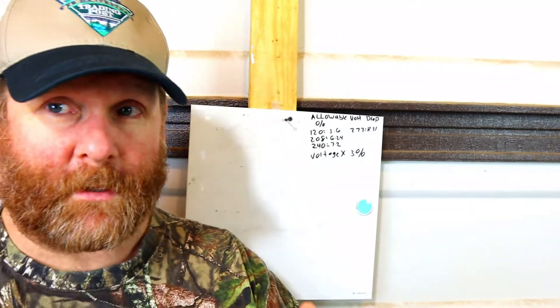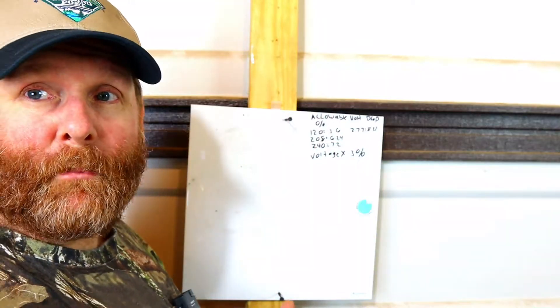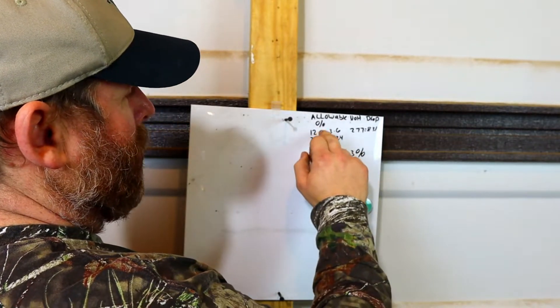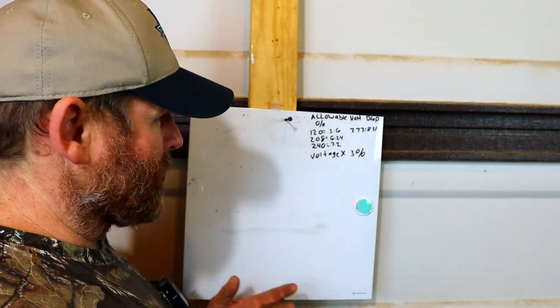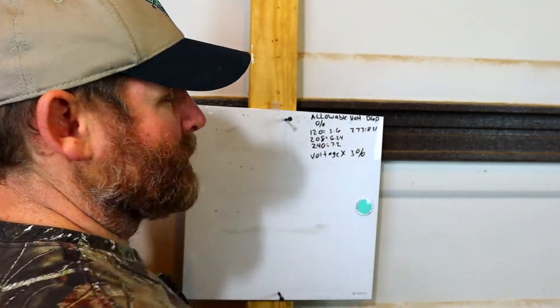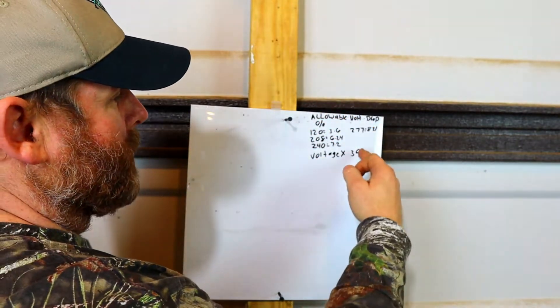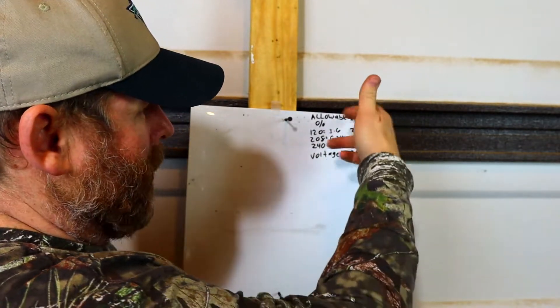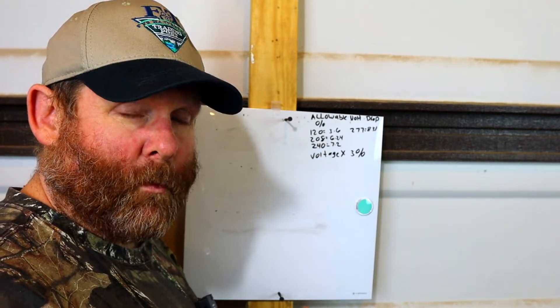First of all, we've got to figure out the allowable voltage drop in percentage, which is 3%. So I went ahead and did the math for you. At 120 volts you can lose 3.6 volts and be okay. 208 volts — 6.24 volts. 240 volts — 7.2 volts. 277 volts — 8.31 volts. You can figure out any voltage by multiplying it by 3%, or 0.03, and you get those numbers.